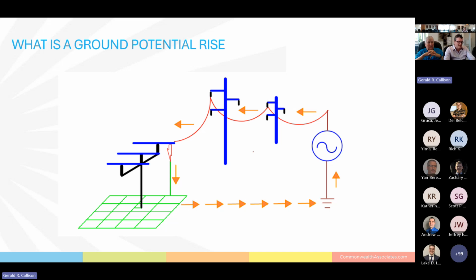As this ground current leaves the ground grid through the grid to soil interface and goes back to remote Earth through that resistance, resistance times current is equal to voltage. And so this ground grid will rise relative to remote Earth. That rise relative to remote Earth is the ground potential rise. So that is a picture of a grounding system with ground potential rise.